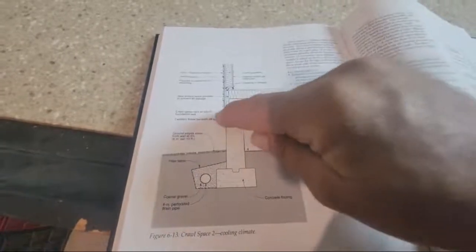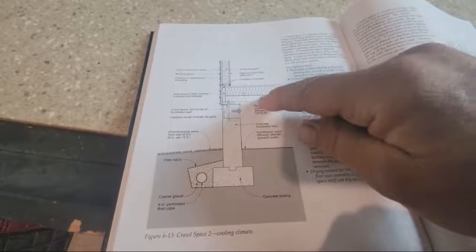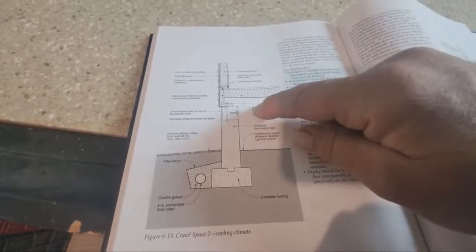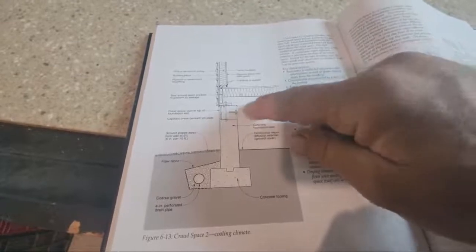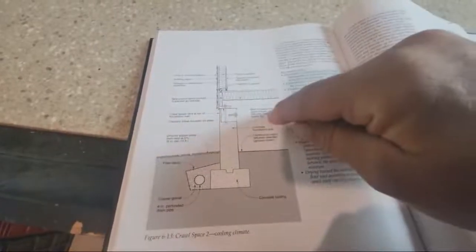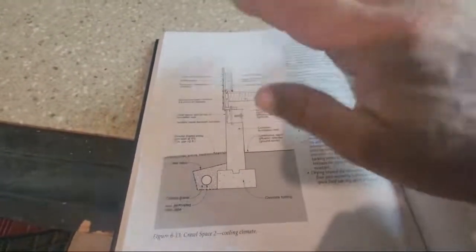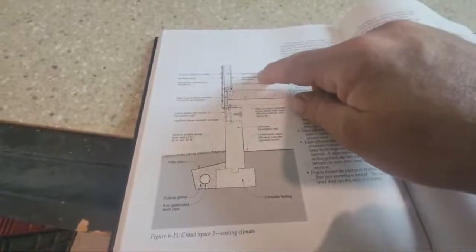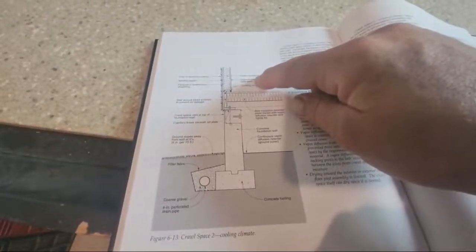You're putting an HVAC system into a non-conditioned space, which means if you have ductwork and the return has duct leakage, it's not sealed, it's going to suck non-conditioned air into here and blow it into the house. This place becomes pressurized, and we have videos on pressurized homes and issues like ice dams.